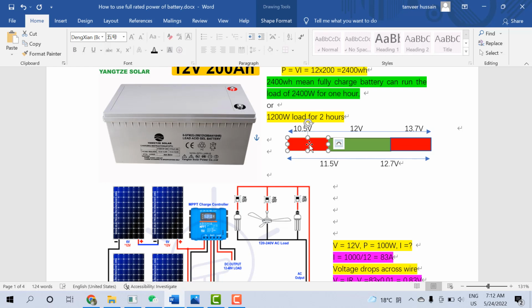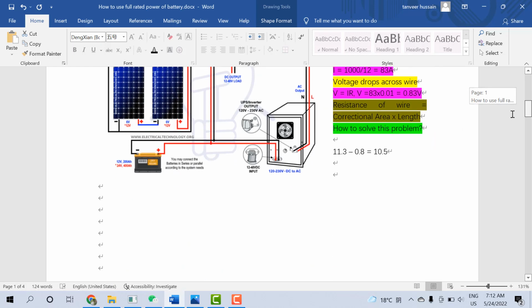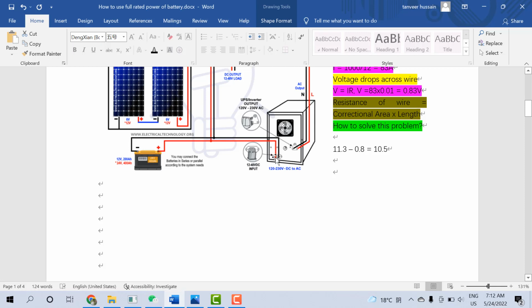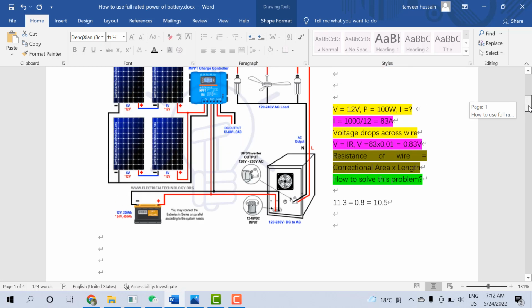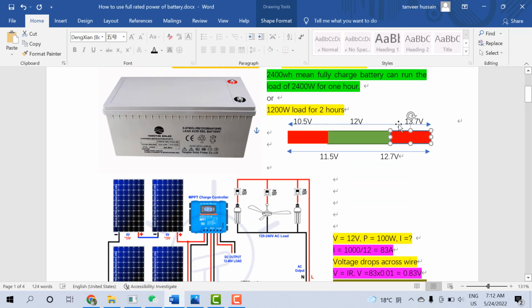I'll explain how to reduce this voltage drop. This was the discharging case. The same thing happens during charging. If you have a voltage drop across the wire during charging, even though your battery hasn't reached maximum voltage, your inverter will read a higher voltage at its end, so it will stop charging.